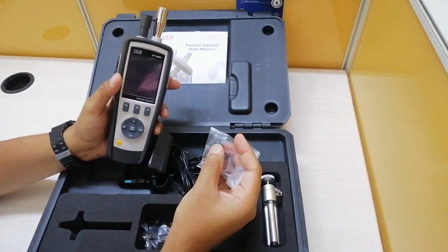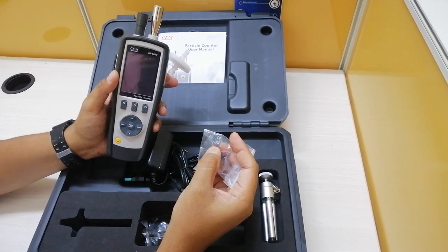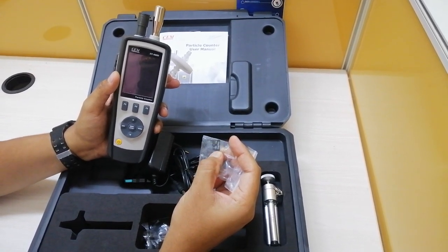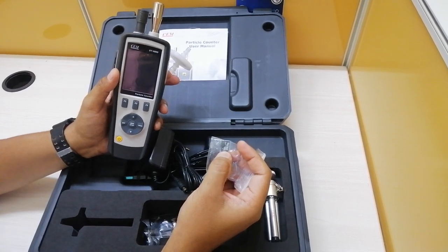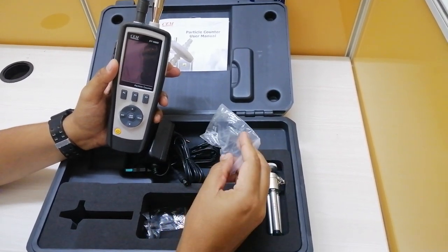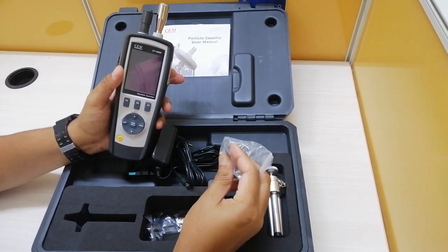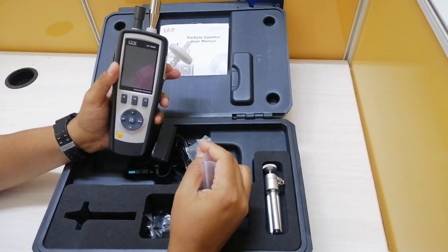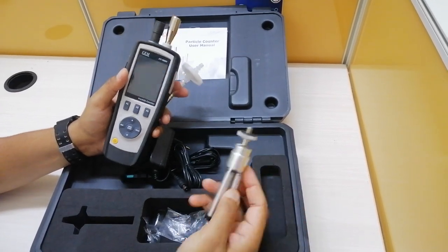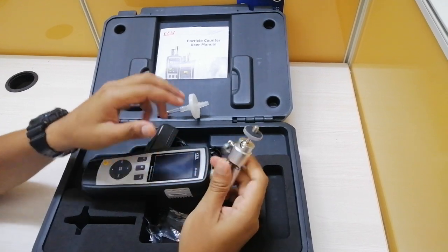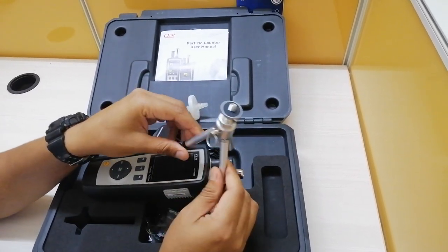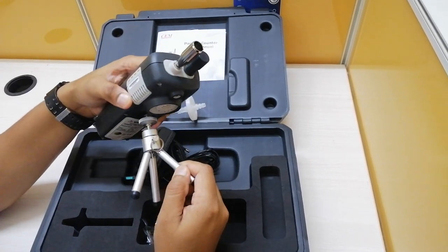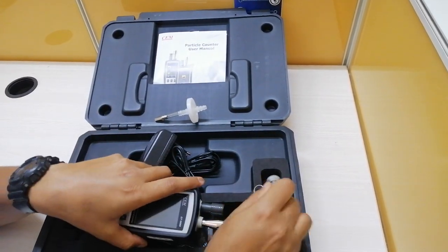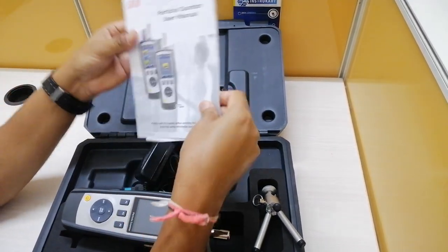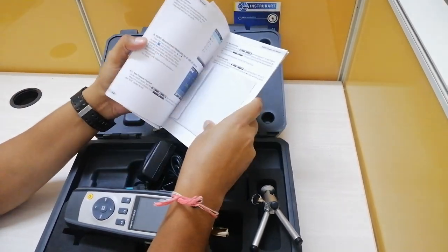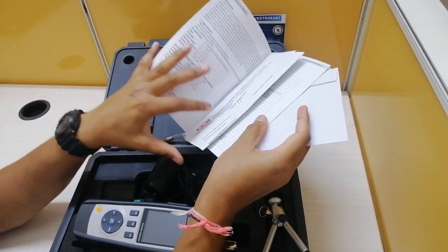We also have an SD card or mini SD card, but please remember that this has to be bought separately and doesn't come in the standard package. I have just taken this extra 8 GB card, and the instrument supports up to 8 GB of memory. To take stable readings, we also have a standard accessory, a tripod. You can fit this and take the readings. Along with this, for documentation, you have the user manual, a CD, and the test report.